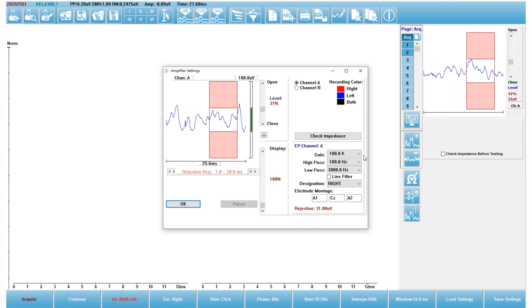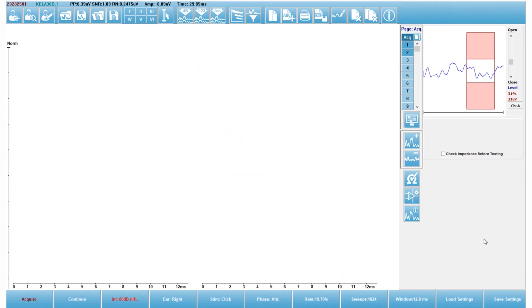and for channel A, I have the gain set to 100,000, which is good. High pass filter 100 Hertz, which is typical for an adult, and my low pass filter is set to 3000 Hertz. And again, because I have some interference in my home office, I'm going to change that to 1500 Hertz. And then I'm going to do the same thing for channel B. In this case, channel A is right ear, channel B is left ear, and I'm going to select OK.